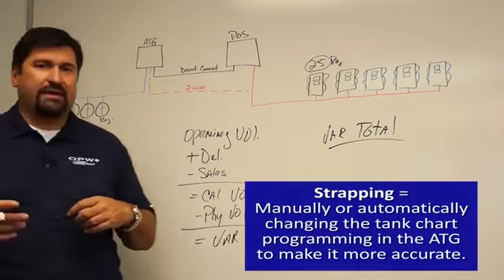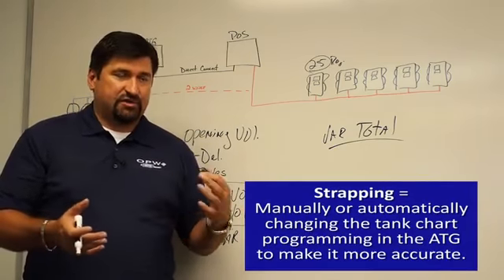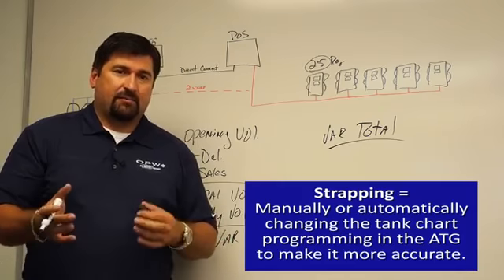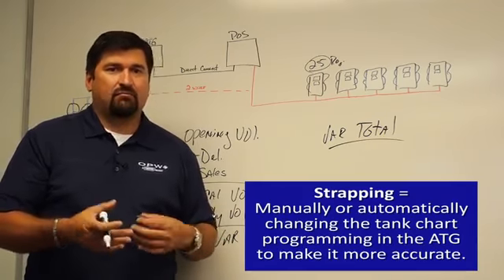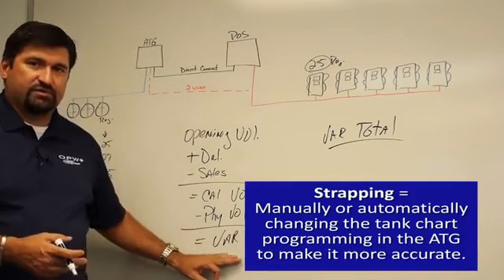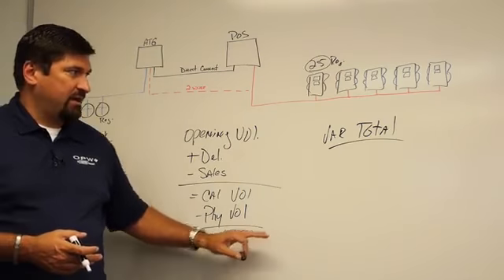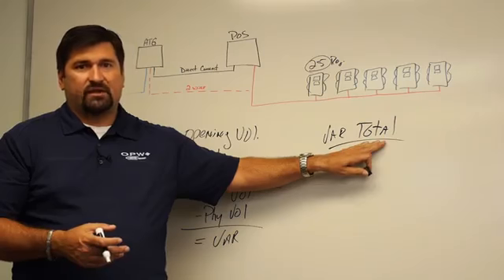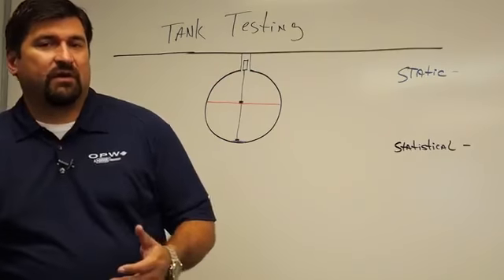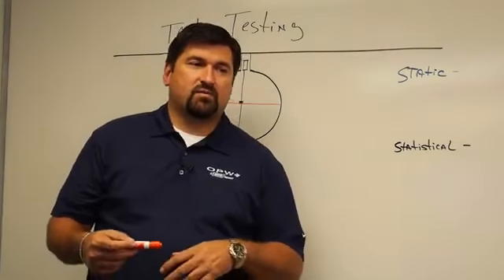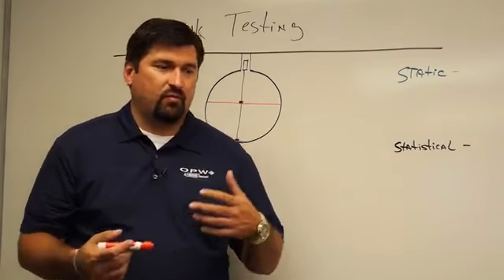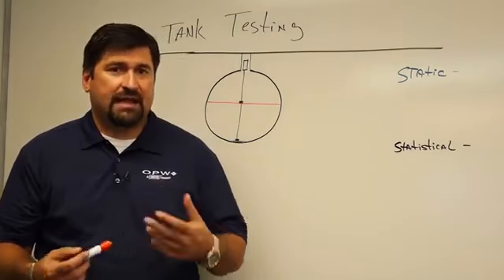So I'm basically recalibrating, or what the industry would call restrapping the tank, to make the tank chart that's in the gauge more accurate, which would reduce the number of variances that you have for the month, bringing your total variance within tolerance. Earlier in the video, we talked about regulatory requirements. Well, when you look at regulatory requirements, the one that we want to go over now is tank testing.